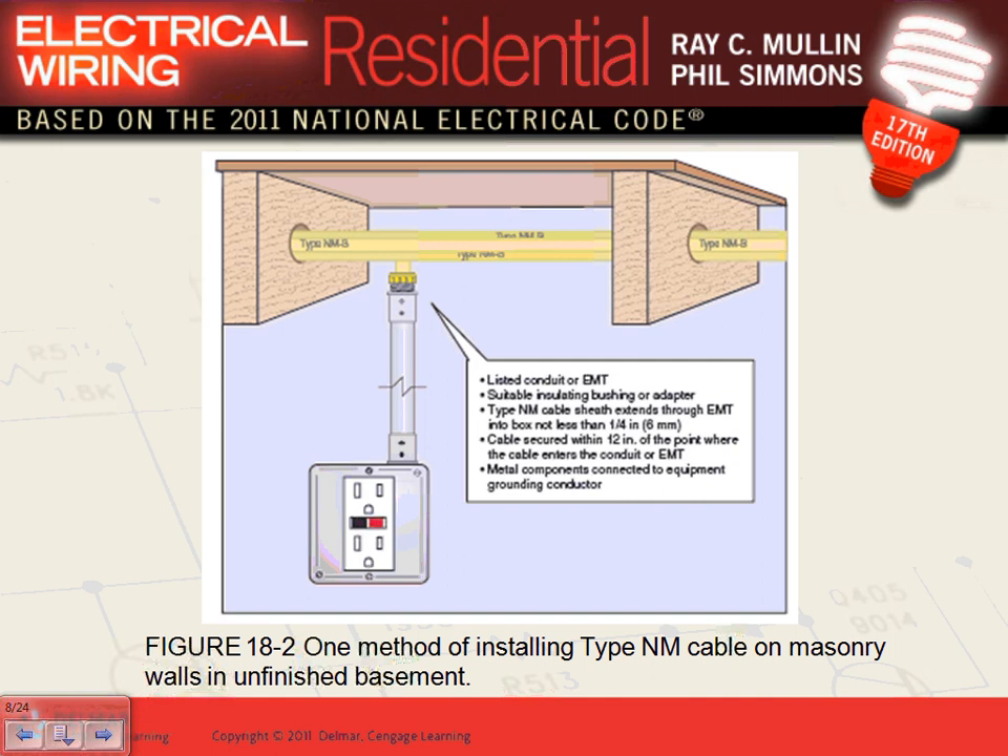There are a couple of rules: the cable must be protected within 12 inches, or at the point where the cable enters the conduit. The conduit must be a listed conduit with an adapter — the adapter is required so you don't damage the jacket of the NM cable as you pull it in. Support the conduit every three feet, and have an insulation bushing where the cable enters the conduit.